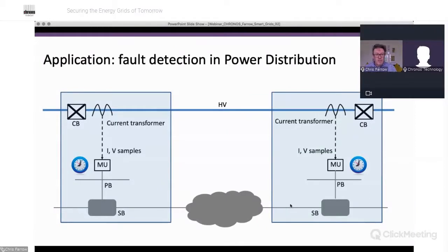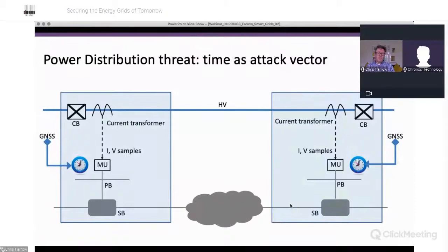In terms of smart grids and the power industry, if we have two separate sites, a site on the left and a site on the right, with high voltage distribution, some current and voltage samples being taken by a measurement unit using a clock reference. If they're both using GNSS, some of these systems do have their own time scales, their own mechanisms to make sure each end uses the same time base. It doesn't necessarily have to be UTC traceable. As long as both ends use the same clock to make a measurement, they can usually get accurate results.